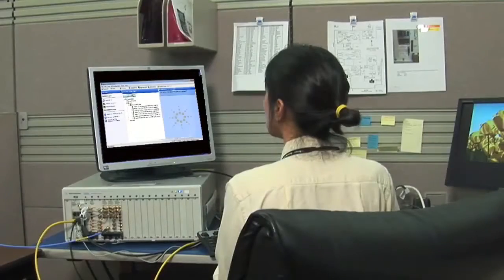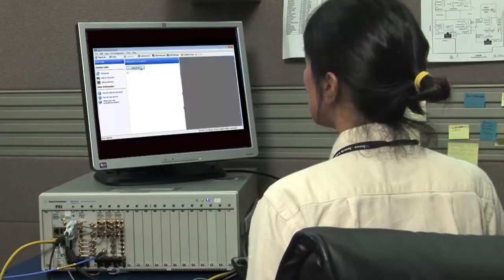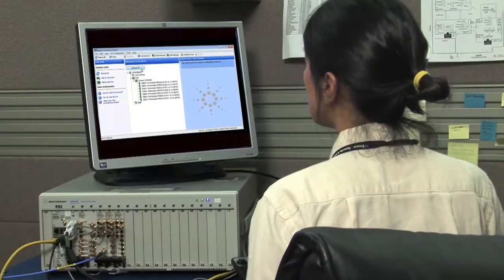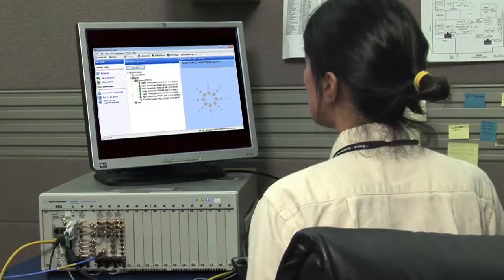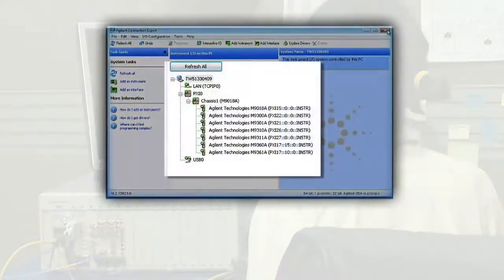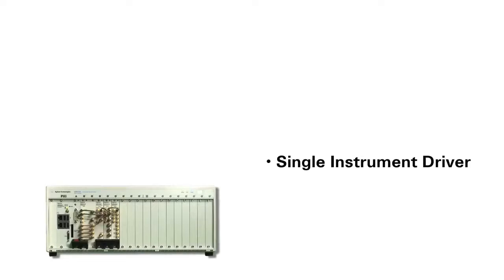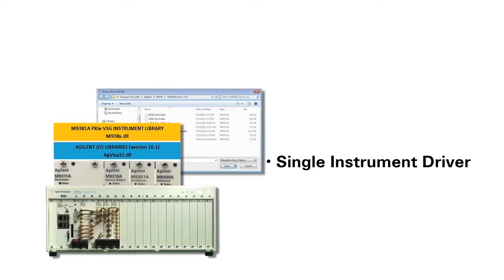To save time in configuring test systems, Agilent's Connection Expert allows easy integration of the M9381A into your PXIE test environment. The Connection Expert display shows all Agilent and non-Agilent PXIE assets. One Step installs the Agilent M9381A driver.